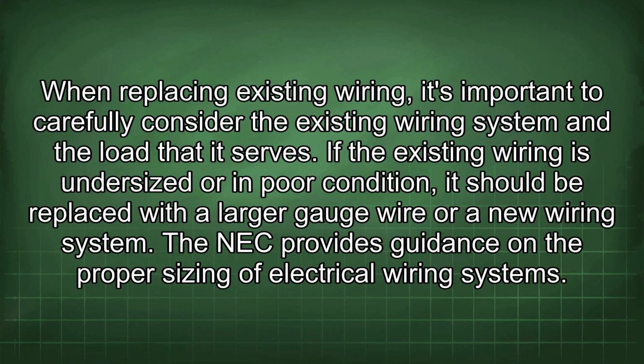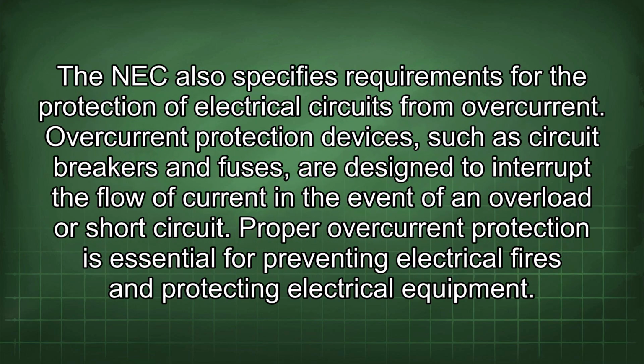When replacing existing wiring, it's important to carefully consider the existing wiring system and the load that it serves. If the existing wiring is undersized or in poor condition, it should be replaced with a larger gauge wire or new wiring system. The NEC provides guidance on the proper sizing of electrical wiring systems. The NEC also specifies requirements for the protection of electrical circuits from overcurrent. Overcurrent protection devices, such as circuit breakers and fuses, are designed to interrupt the flow of current in the event of an overload or short circuit. Proper overcurrent protection is essential for preventing electrical fires and protecting electrical equipment.